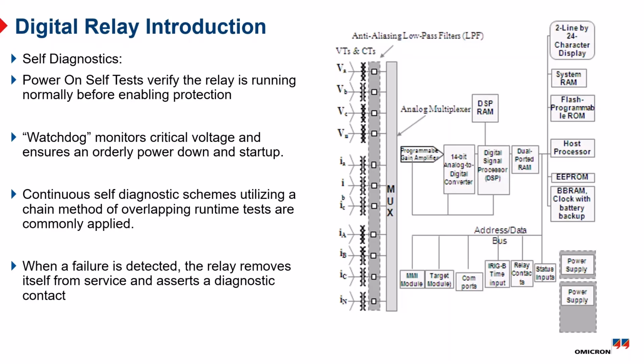Station battery that was powering the relays goes dead. We don't want the program pointer in the relay to lose its place and start executing lines of code that it's not supposed to. So the relays are designed to have an orderly startup and an orderly shutdown. Voltage goes to an unsafe level, the watchdog shuts the device down before anything bad can happen. And then when the relay is started up, it has an orderly startup.